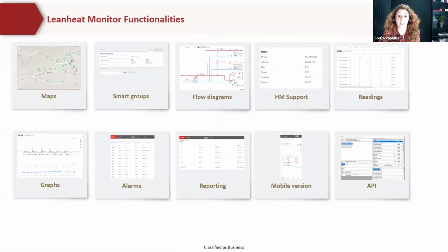So with this intuitive software, you can access a wide range of functionalities, and it's so important when you're looking at the controllability of your product that you've got on site. So not only is selecting the right heat exchanger and selecting the right valve important, but actually understanding how they're working and how your system is operating. With this software, you're able to get a number of different functionalities, including maps, flow diagrams, real life data, understanding what your flow and return temperatures are and what you're actually delivering from your heating circuits and your domestic hot water. You're able to download the files as CSV files, and you're also able to create charts and graphs so that you can actually prove and show how your system is operating.